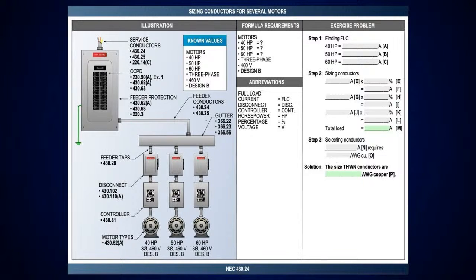And like I tell everybody, go look at other publications. You won't see this. And you know why? It takes a lot of time to go check all them sections. It just goes to show the amount of work, effort and time we put into this stuff. And like this in here, we show 3 motors. You've got a 40, 50, and 60. All you have to do is get the largest motor, which is going to be 60 horsepower, take it at 125%, add all the rest at 100%, get your total amperage, go to table 310.16, 75 C column, and find the conductor that's above it. It's that simple.